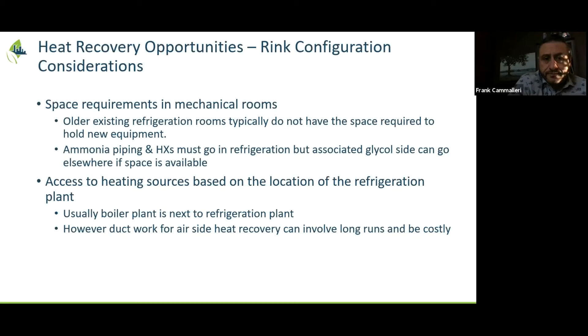Access to heating sources based on the location of the refrigeration plant is a big factor. The good thing is we've found that usually boiler plants are next to the refrigeration plant, so that part is fairly easy. Heat recovery is a complex thing, and it is very custom to the specific rink, how you can access it, and the space available for it. Even though the focus for low carbon is typically around getting as much heat out as you can, there are constraints you need to be mindful of.